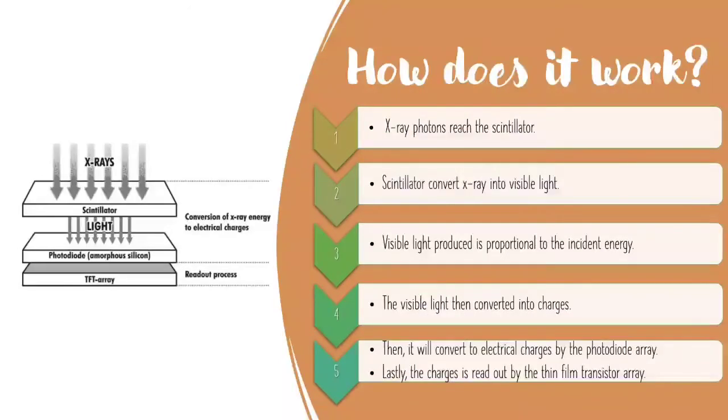So how does it work exactly? First, the x-ray photons reach the scintillator. The scintillator then converts x-ray into visible light. Visible light produced is proportional to the incident energy. The visible light is then converted into charges, then converted to electrical charges by the photodiode array. Lastly, the charges are read out by the thin film transistor array, or TFT.